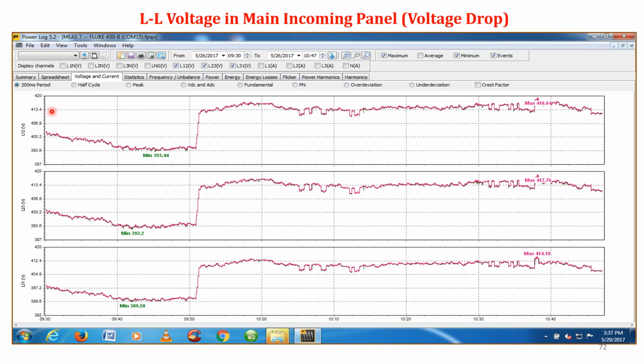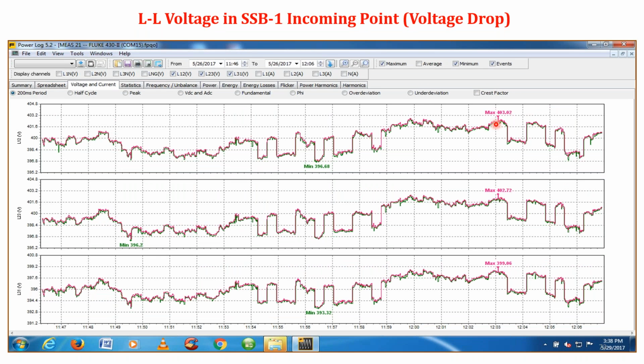It is recorded 410 and 412 voltage in the supply power side in one particular DB. The same DB is measured at the location side. The voltage drop is going to be 400. Now the 10 to 12 voltage drop is what was experienced during our measurement.